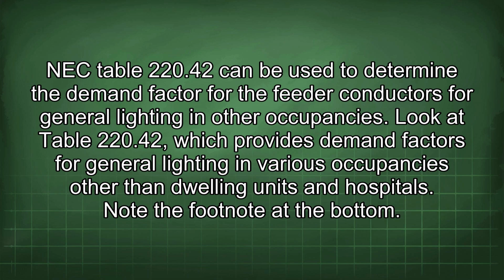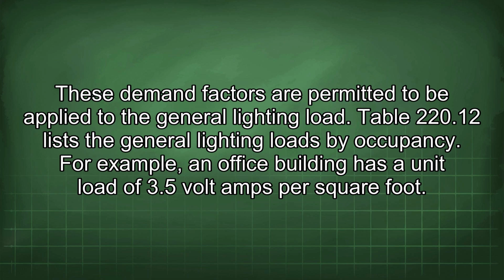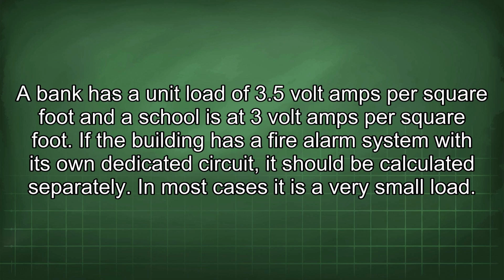NEC Table 220.42 can be used to determine the demand factor for the feeder conductors for general lighting in other occupancies. Look at Table 220.42, which provides demand factors for general lighting in various occupancies other than dwelling units and hospitals. Note the footnote at the bottom. These demand factors are permitted to be applied to the general lighting load. Table 220.12 lists the general lighting loads by occupancy. For example, an office building has a unit load of 3.5 volt amps per square foot. A bank has a unit load of 3.5 volt amps per square foot, and a school is at 3 volt amps per square foot. If the building has a fire alarm system with its own dedicated circuit, it should be calculated separately.